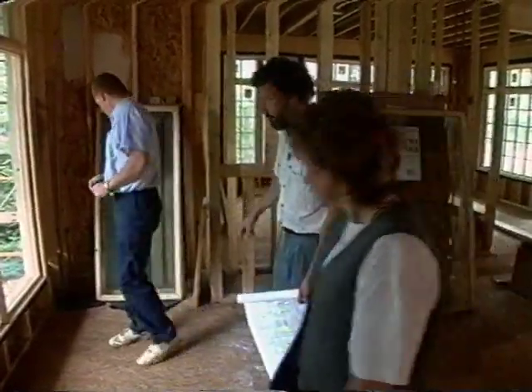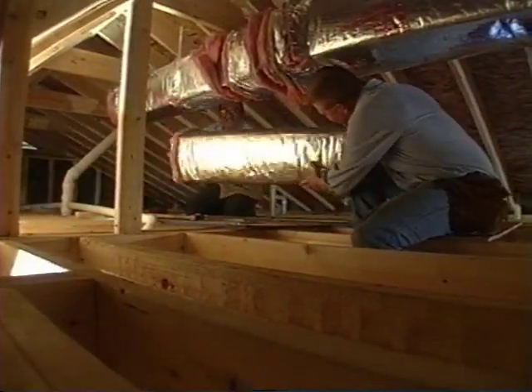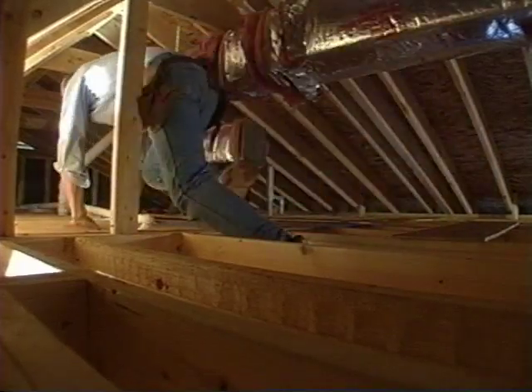The design of the air distribution system can affect more than comfort — it can also impact the health and safety of homeowners. Many people complain about closing their bedroom doors at night only to have the room get hot and stuffy. Not to mention the indoor air quality aspects: if some rooms are going positive pressure, obviously some rooms are going negative pressure. When that happens, they can carry contaminants with them, you can get backdrafting of equipment, and it becomes a real health risk.